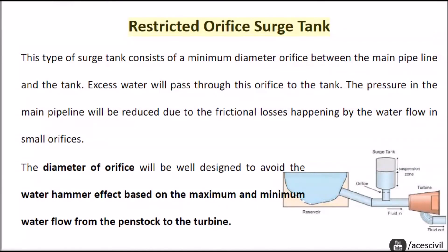Restricted orifice surge tank: This type of surge tank consists of a minimum diameter orifice between the main pipeline and the tank. Excess water will pass through this orifice to the tank. The pressure in the main pipeline will be reduced due to the frictional losses occurring from water flow through the small orifice. The diameter of the orifice is well designed to avoid the water hammer effect, based on the maximum and minimum water flow from the penstock to the turbine.